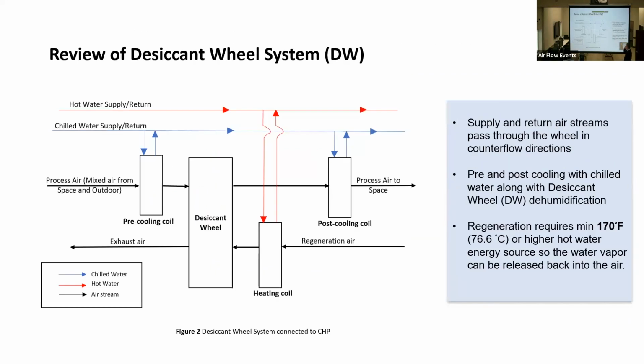What we're being compared to in this particular case, again, this is another vendor's system. They have a pre-cooling coil, wheel, and a post-cooling coil, and then they are using the hot water system to do the regeneration of the wheel. And the systems work. They're fine. We were looking at it from an energy savings point of view, and that data is starting to trickle in now. Both those systems are fully instrumented for power usage. Every single component, whether it's fans or controls, you name it, has energy measuring devices on it. And after several 9-week growing cycles, we'll have a full data set.